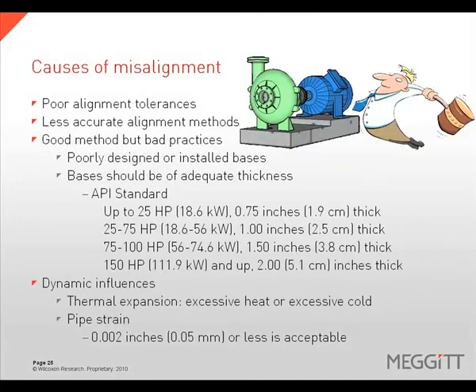There are many causes of misalignment, including using poor alignment tolerances when performing alignments, using less accurate methods of alignment like a straight edge, using good methods but bad practices such as poorly designed bases, and dynamic influences like thermal growth or pipe strain.